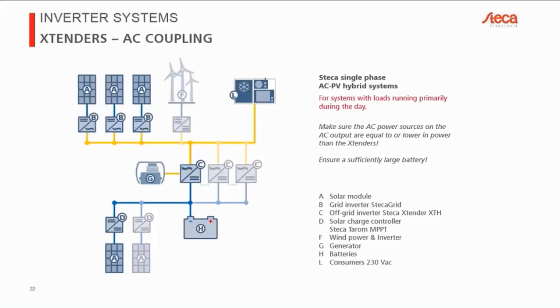As I mentioned, the Xtenders have a bidirectional AC output. What this means is that even in a completely off-grid environment where you have absolutely no connection to the grid, you can use grid inverters. What you see here would be the Xtenders, connected to the battery. On the AC output, you have your loads, which is the normal setup we had initially during the session, where your AC loads are connected.